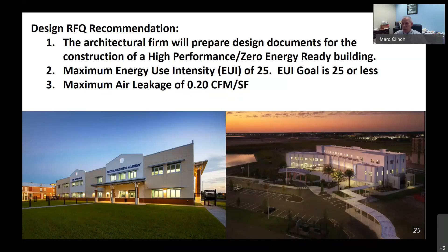And the maximum air leakage I would recommend is 0.20 cubic foot per minute per square foot. As I mentioned, we have been exceeding this criteria as well. We've been getting anywhere from 0.027 to 0.046 has been our worst reading on all our blower door air leakage tests thus far. So that 0.2 is something that's very achievable.